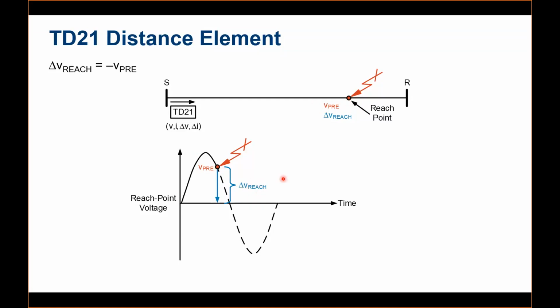So the relay is estimating or calculating the reach voltage for each fault, and it is compared with your setting. That's coming in the next slide. The relay will be using the change in the voltage and the change in the current. And remember, this is not phasor based. We are just taking the samples on the waveform and comparing with the previous sample. For phasor-based, you need to wait at least half a cycle or a full cycle to convert into phasors and take action. That's why this is much faster compared to phasor-based, because we are not dependent on phasors.